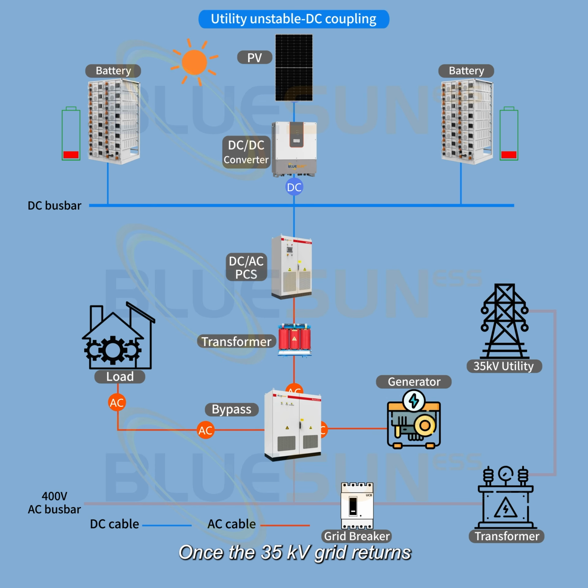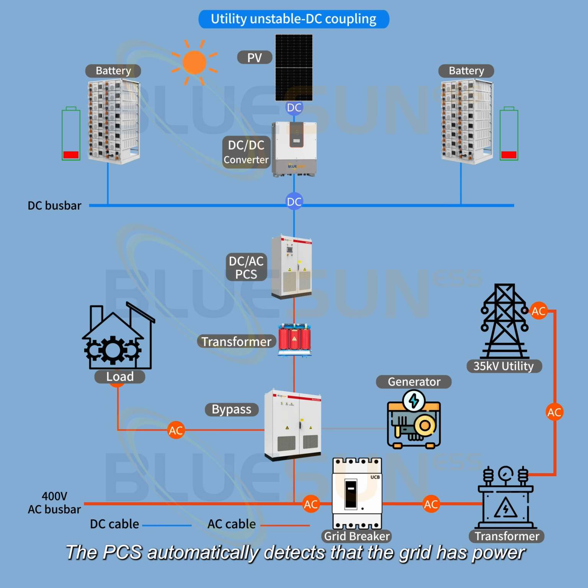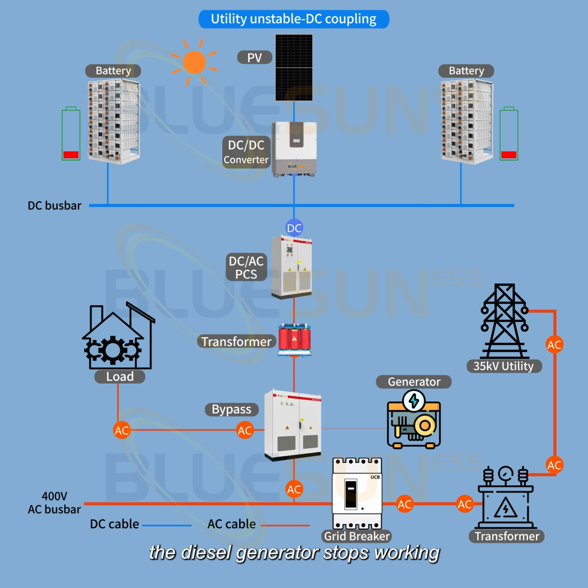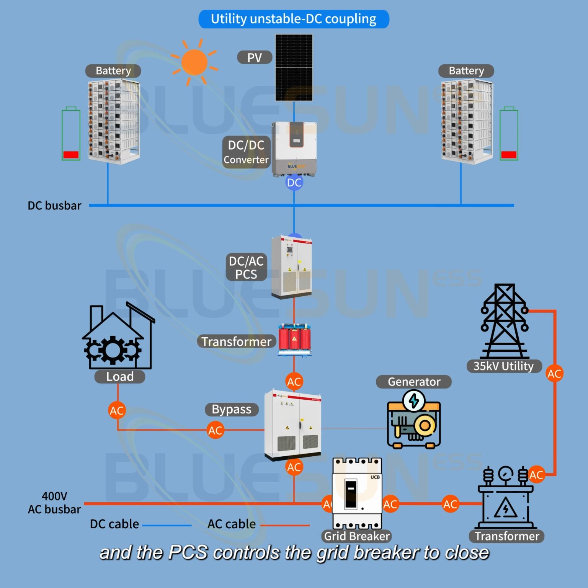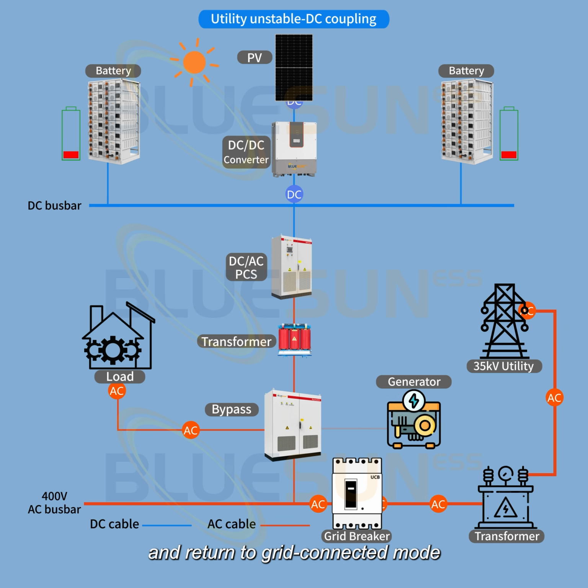Once the 35 kV grid returns, the PCS automatically detects that the grid has power, the diesel generator stops working, and the PCS controls the grid breaker to close and return to grid-connected mode. The grid directly supplies power to the load through the bypass.